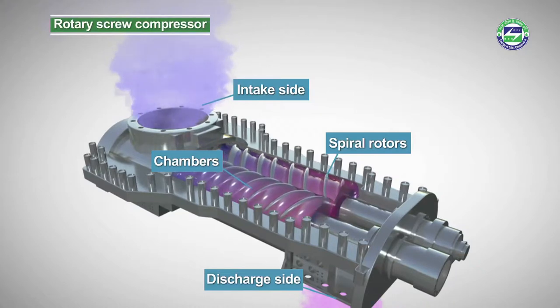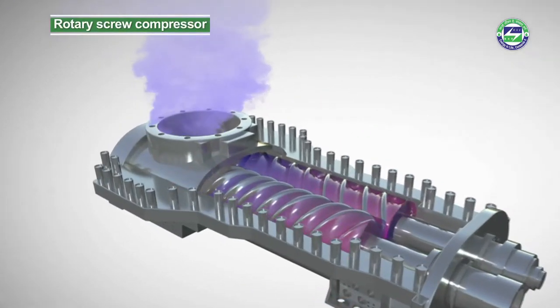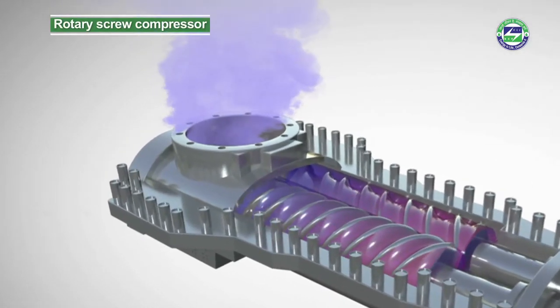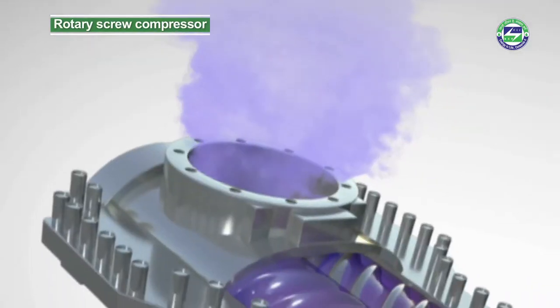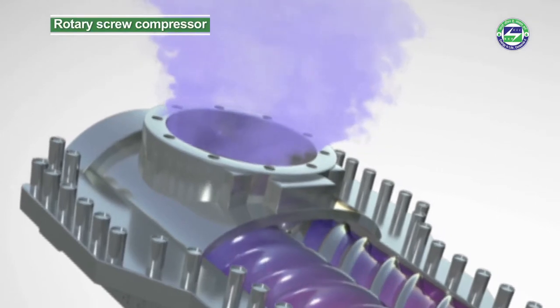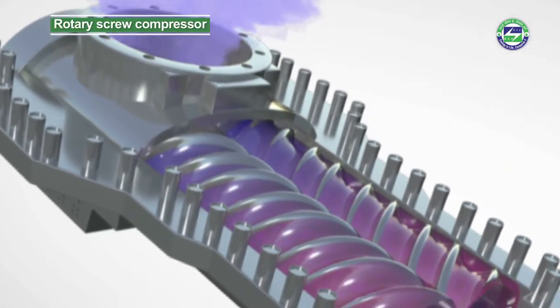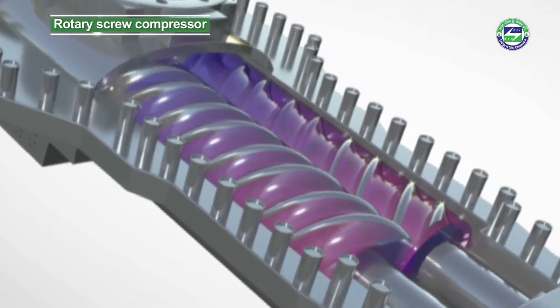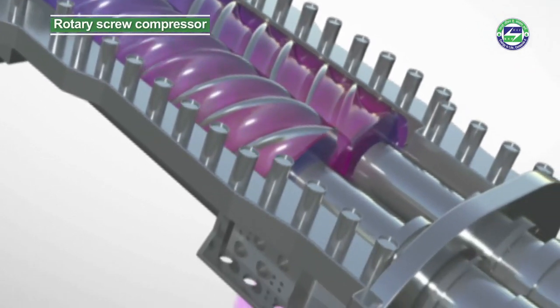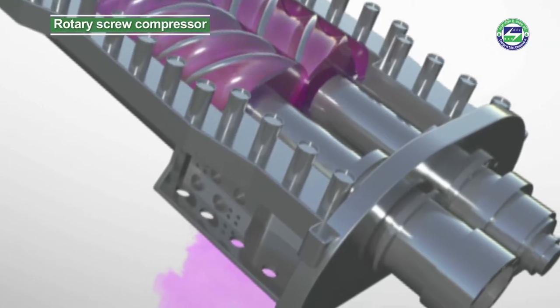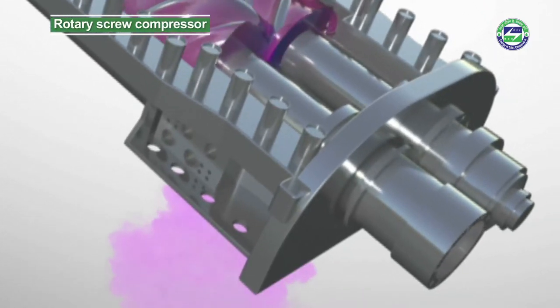Rotation causes the chambers to move from the suction or intake side to the compression or discharge side. These chambers are connected to the suction nozzle via ports; as the chambers enlarge, they are filled with air flowing in through the nozzle. The rotor transports the gas towards the discharge side where the chamber shrinks and the retained air is compressed. Once the air is compressed, the chamber reaches another port connected to a discharge nozzle.